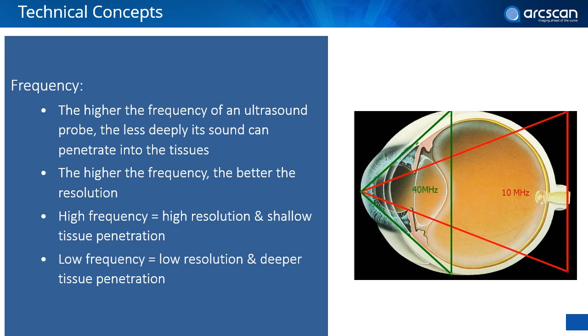In the case of the Insight 100, when we evaluate the cornea, we use a 50 megahertz probe, which allows us to see detailed structures like the epithelium and Bowman's membrane of the cornea. This is because the higher the frequency, the less deeply its sound can penetrate into the tissues, yes, but it also means that the resolution is better.